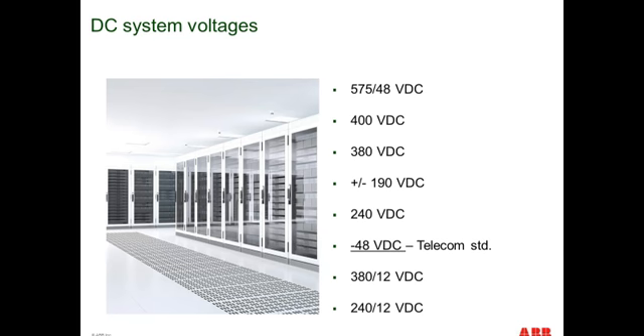First, I wanted to review some of the voltages associated with those systems. So early on, when DC was first being considered for use in data centers, there were two different schools out there. One was an Intel EPRI PIAC model that revolved around feeding 380 volts directly to a server. Another was a hybrid system where 575 volt DC was distributed through a building and stepped down to 48 volts at or near the point of load. The intent of that original system was to make 48 volt DC infrastructures scalable based on the increasing power densities we were seeing in the marketplace.